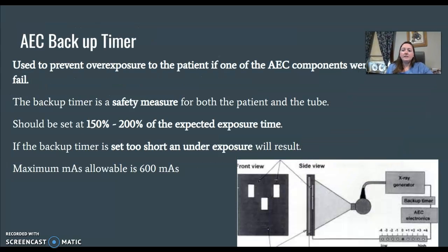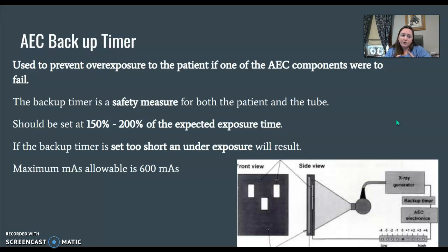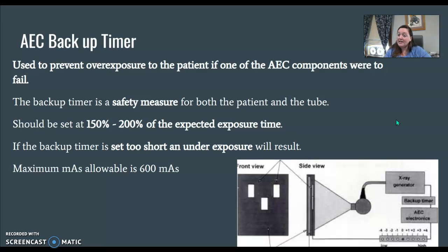The backup timer. AEC has a backup timer. It's used to prevent overexposure to the patient and protect your equipment — it's a safety measure. There is a backup timer in case the AEC does not turn off at the appropriate exposure time. It's going to be set to at least 150% to 200% over what it expects the exposure time to be for that part. If the timer is set too short, it will result in underexposure. The maximum mAs allowable is 600 mAs. So if you get a question about a backup timer, that's what that is.